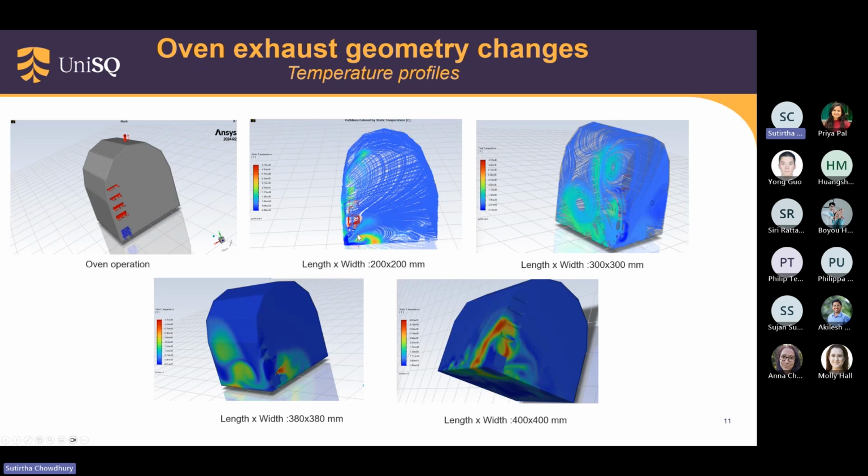Though it gives 225 degrees Celsius in some points, and the ducts are getting almost 373 degrees Celsius, it is not good enough to give 250 degrees Celsius all over the oven.